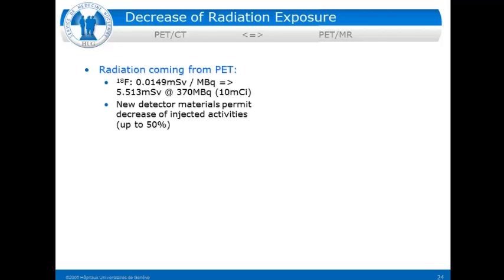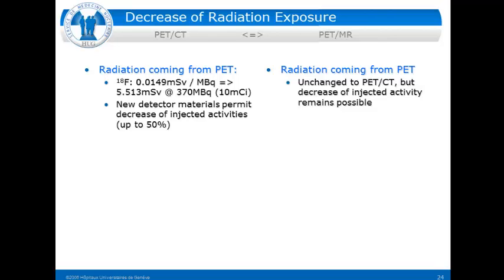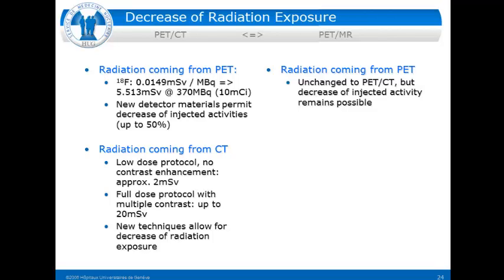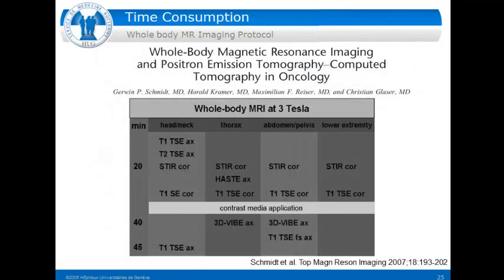On radiation exposure: depending on the activity injected, we are up to five or a little more millisieverts from PET, but new detector materials now permit decreasing injected activities by up to 50 percent. This is unchanged in the PET-MR system. From CT, low-dose protocols exist — in cardiac imaging without contrast you can go down to two millisieverts, but full-dose protocols reach 10 to 20 millisieverts — so the main potential for dose reduction comes from CT. Of course, there is no irradiation from MR.